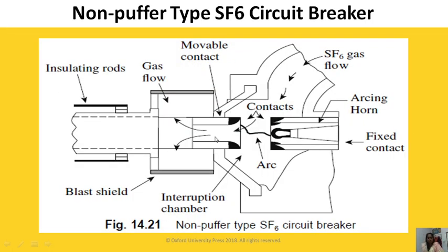In the non-puffer type, the fixed contact and moving contact are present. As soon as a fault occurs, the relay gives a tripping signal to the circuit breaker, the contacts open, and an arc forms. SF6 gas comes from the reservoir and quenches the arc. The gas exits through the rectangular holes provided on the movable contact, which serve as outlets for gas flow.